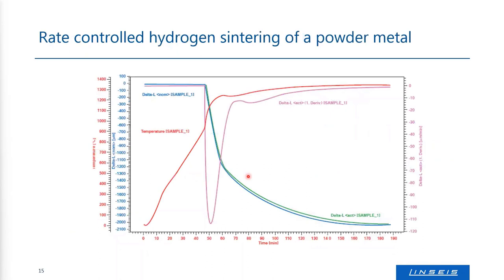The sintering process can be optimized using special software called rate-controlled sintering software. The length change or density of the sample is programmed — you enter the desired density profile, and the furnace regulates the temperature to achieve it. This can optimize the production process to achieve the highest possible density and save energy costs by avoiding unnecessarily high temperatures.